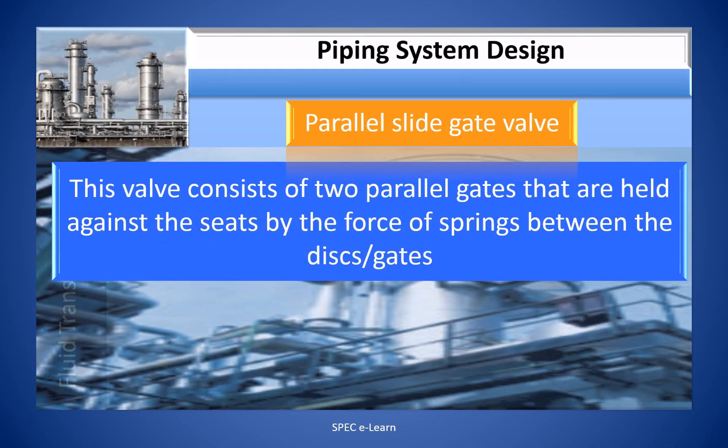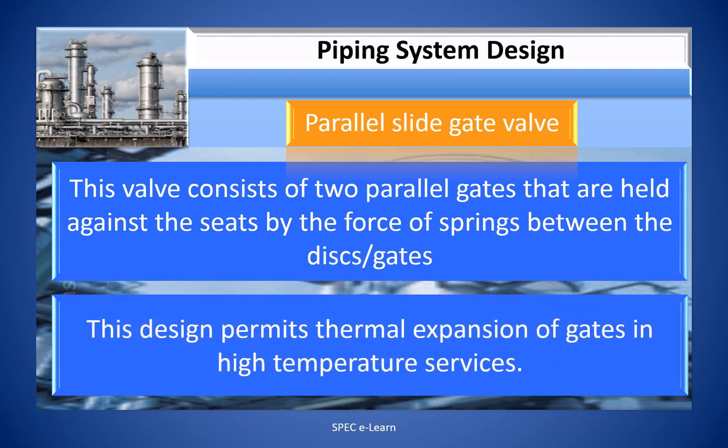The parallel slide gate valve consists of two parallel gates that are held against the seats by the force of springs between the discs or gates. This design permits thermal expansion of the gates in high-temperature services.